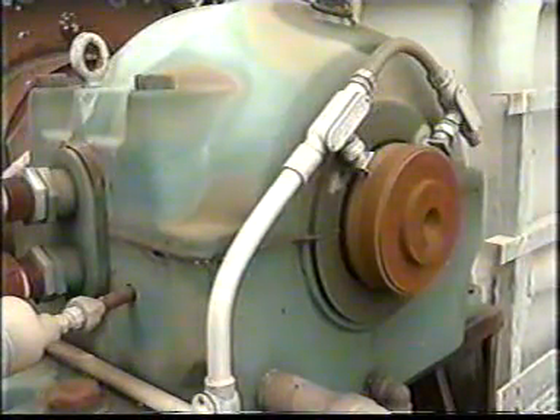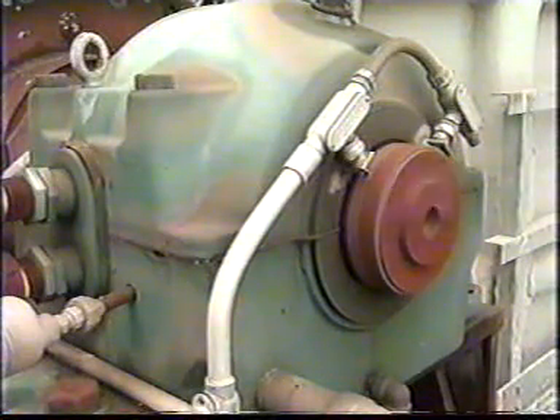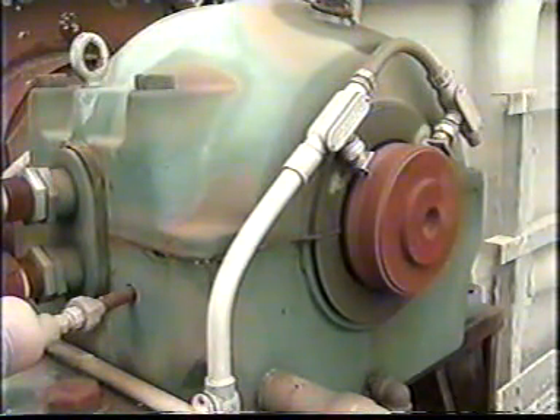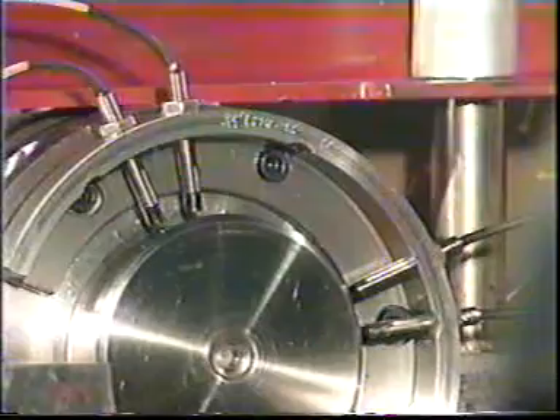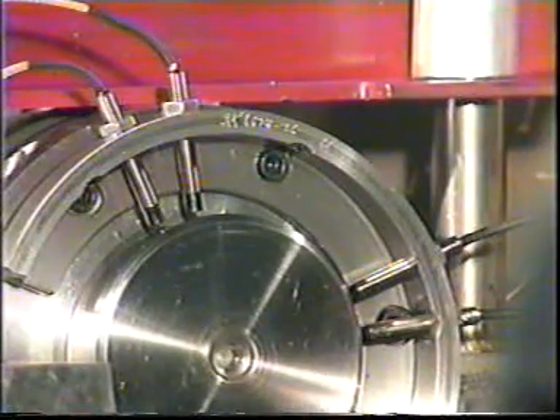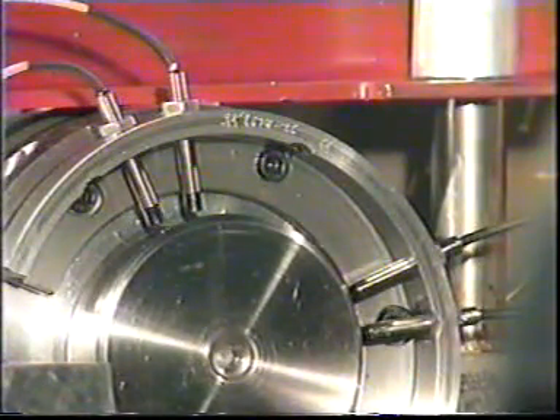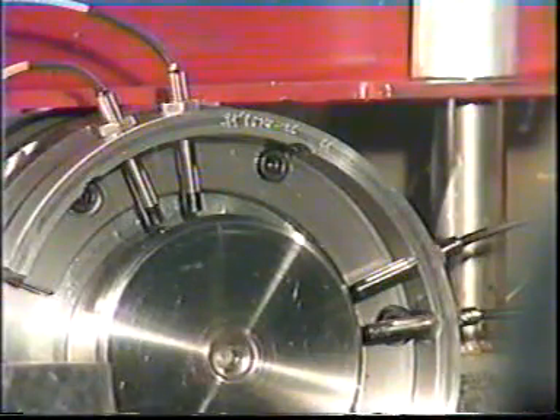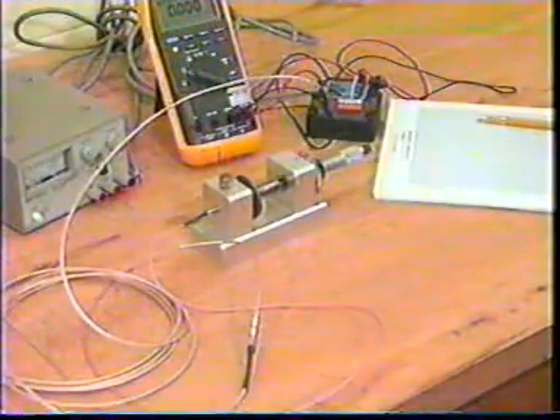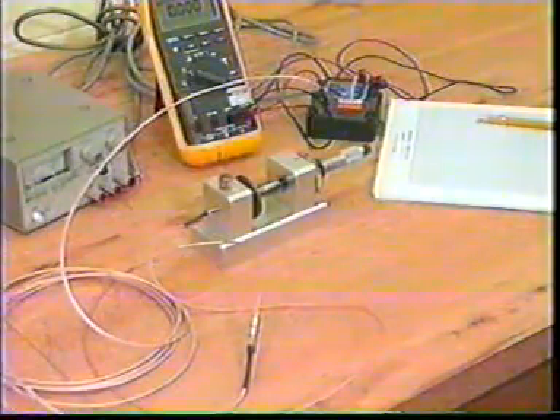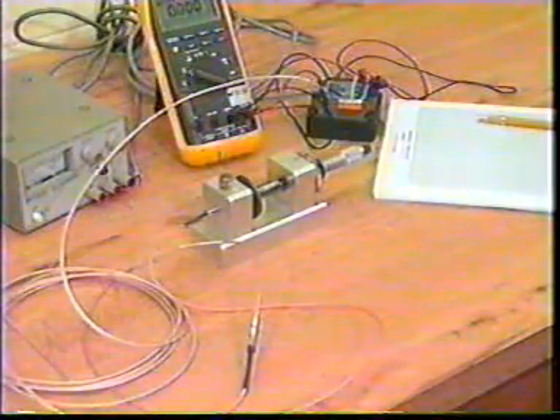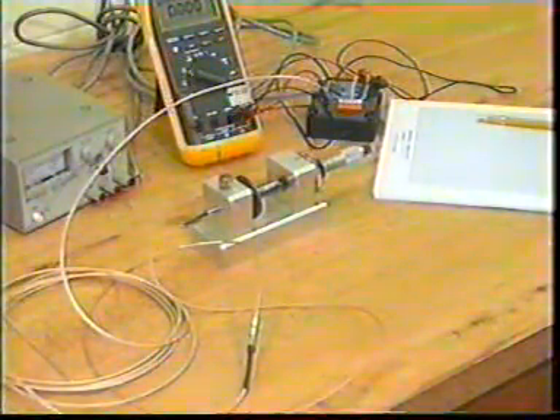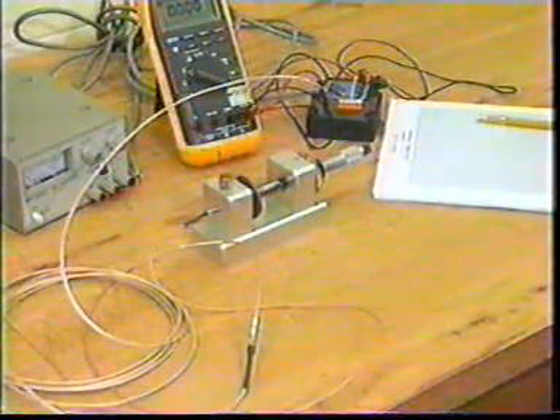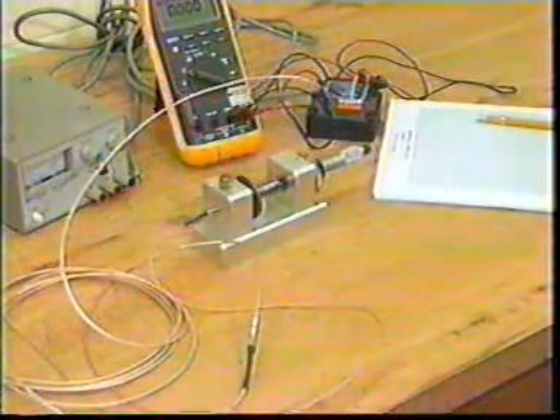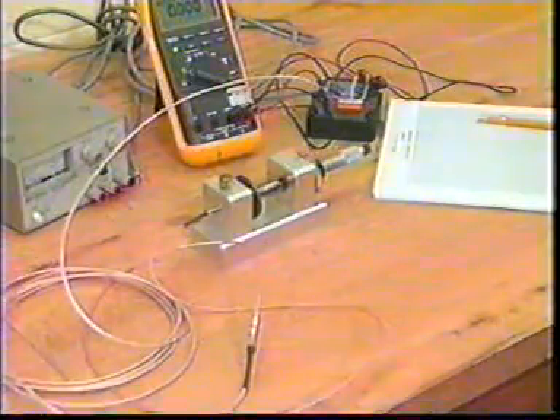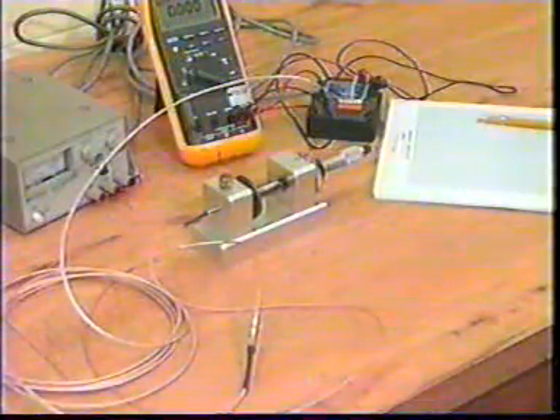Target characteristics, such as permeability and conductivity, affect proximity probe calibration. For example, a stainless steel shaft will have different permeability than a carbon steel shaft. The calibration device target material needs to be the same as the shaft material for accurate calibration. Also, the shaft surface will affect proximity probe output. Take care to keep from scoring or scratching the shaft.